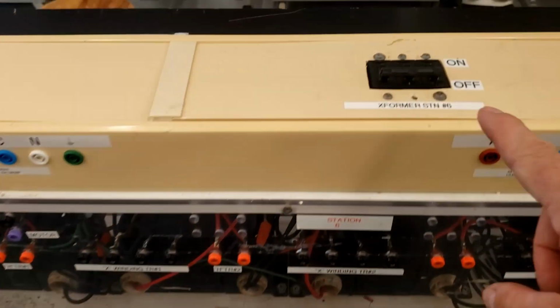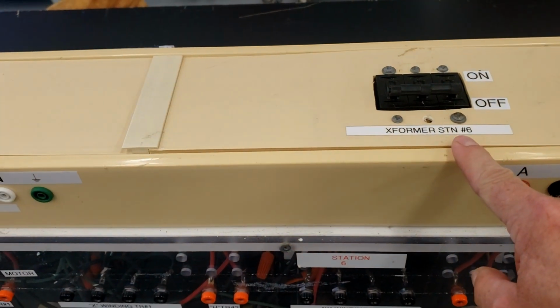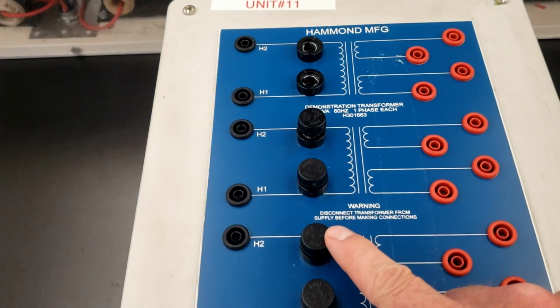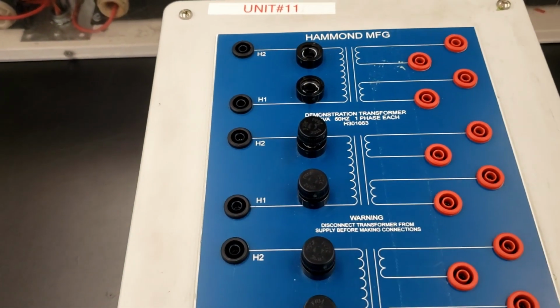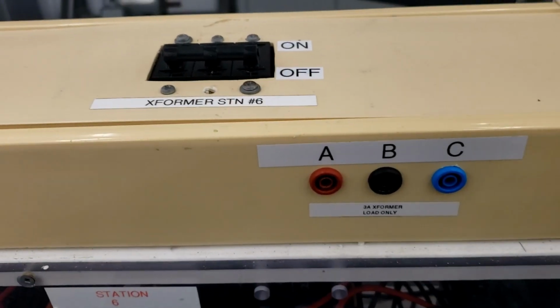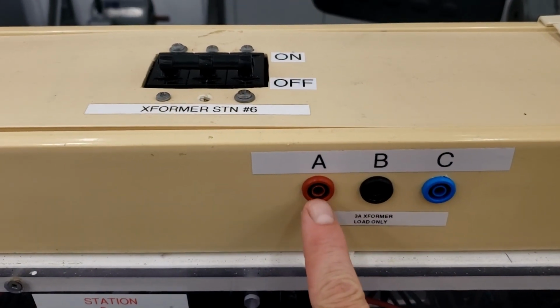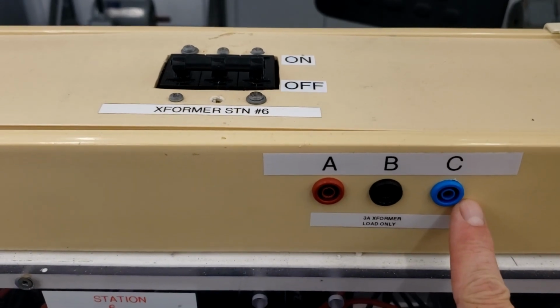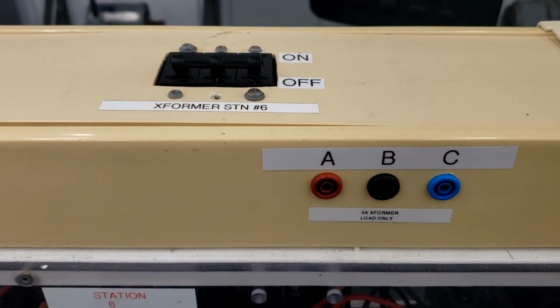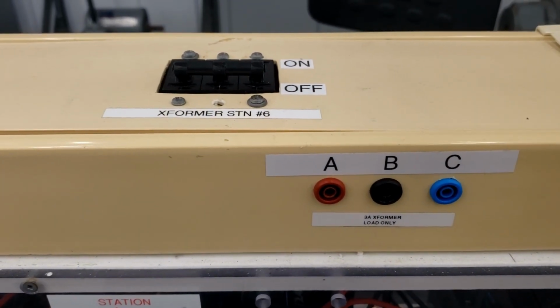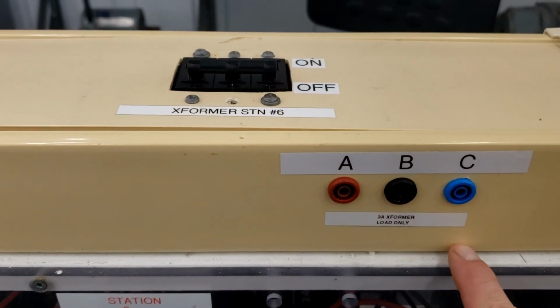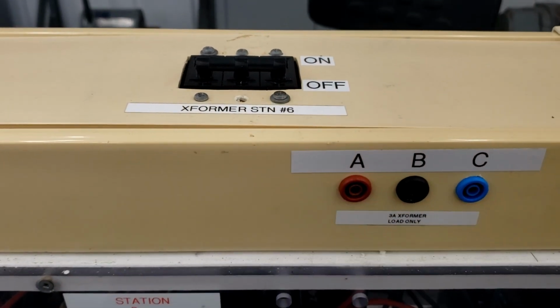So we're going to make use of the 3 amp breaker, and we're making sure that we're using the 1/4 amp fuse on each of these inputs on the primary of the transformers. That 3 amp breaker has 3 connections here. So we got line 1, line 2, and line 3. There's 208 available in the room. So you'll have 3-phase 208 available here, but limited to 3 amps on this breaker.